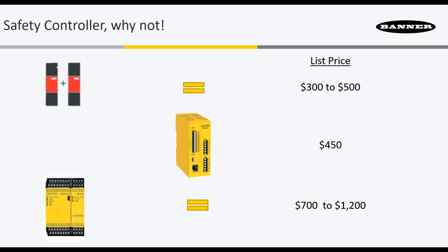It depends on what category you're trying to achieve with your e-stop. If you want to go with a 4-wire dual channel system, it has the ability to have pulsed outputs that are independent for each channel. That gets you to your highest category rating. Sharing the pulse in a 3-wire system with those 2 channels is another way to do it. So those are the 2 typical ways. I mean, there are single channel e-stops out there as well. Our controller supports all of it, so it depends on what's required for your machine based on the risk assessment. And in our controller, it's flexible with whichever wiring configuration you select or whatever device you need.